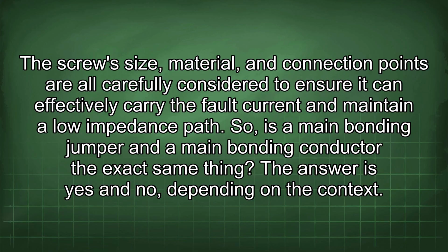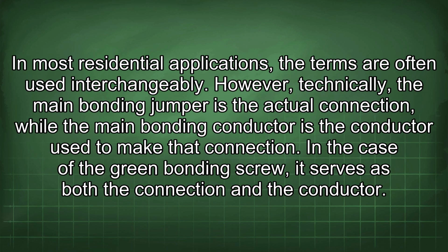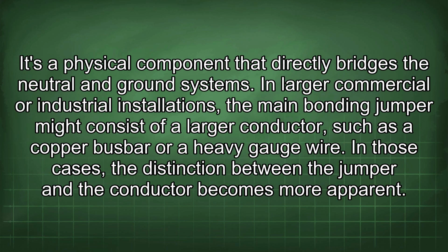So, is a main bonding jumper and a main bonding conductor the exact same thing? The answer is yes and no, depending on the context. In most residential applications, the terms are often used interchangeably. However, technically, the main bonding jumper is the actual connection, while the main bonding conductor is the conductor used to make that connection. In the case of the green bonding screw, it serves as both the connection and the conductor. It's a physical component that directly bridges the neutral and ground systems.